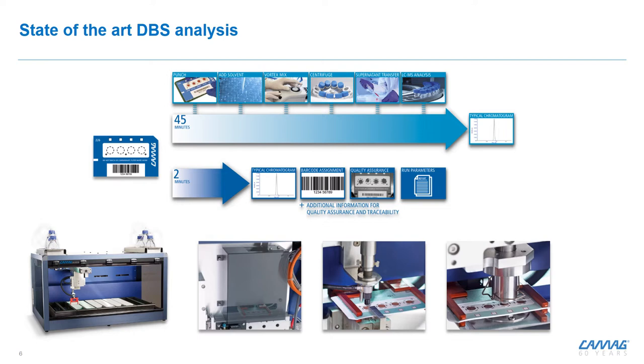The DBS-MS500 instrument, which you can see in the bottom left of the picture, has three modules. First, there is a camera where we scan the barcode and the shape and location of the dried blood spot. Then we can apply internal standards directly on the dried blood spot, which allows us to do quantification as we can nullify for the hematocrit-based recovery bias. And then we directly elute from the filter paper into the LC-MS instrumentation.